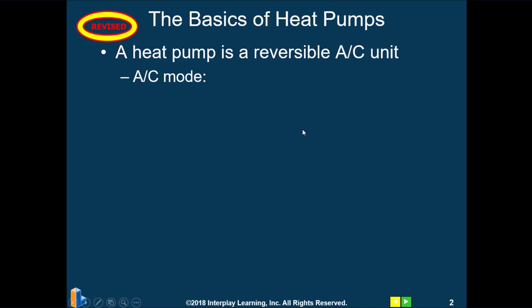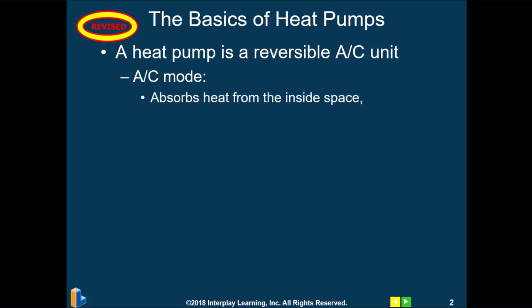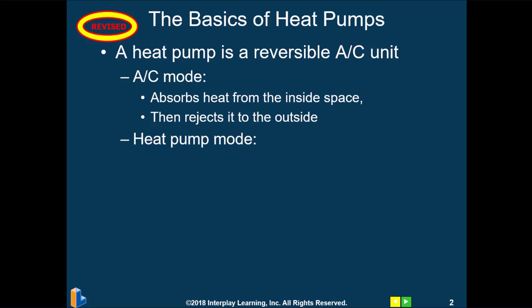In the air conditioning mode, it functions just like a regular air conditioner. Discharge gas coming out of the compressor is routed to the outdoor coil, which is operating as a condenser, where it de-superheats, condenses or changes state, and sub-cools the refrigerant. That refrigerant is then sent through the liquid line to the indoor coil, which is operating as an evaporator. It absorbs heat from the inside space and rejects it to the outside in the outdoor unit.